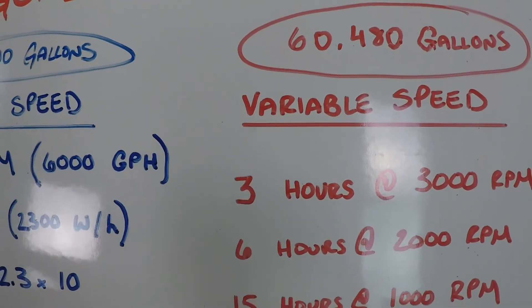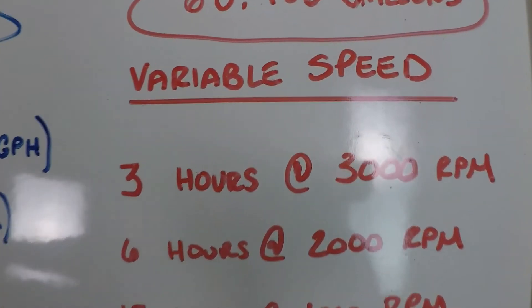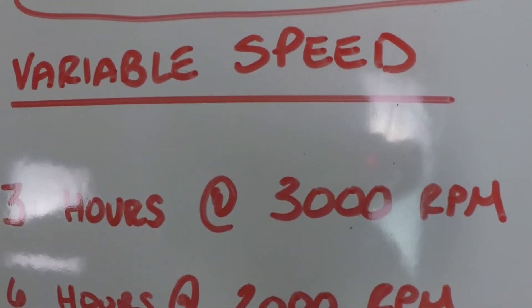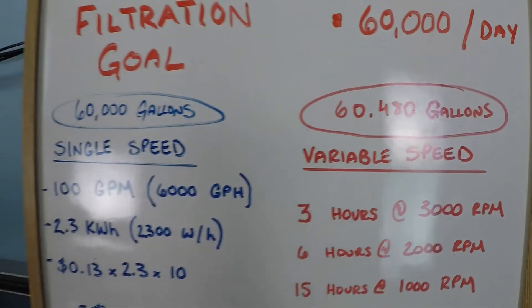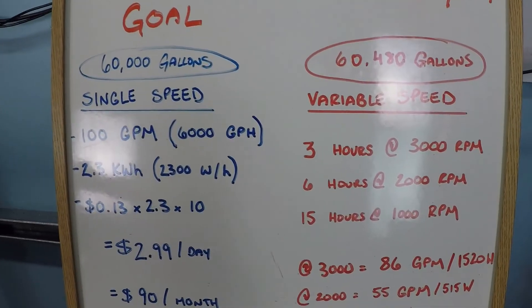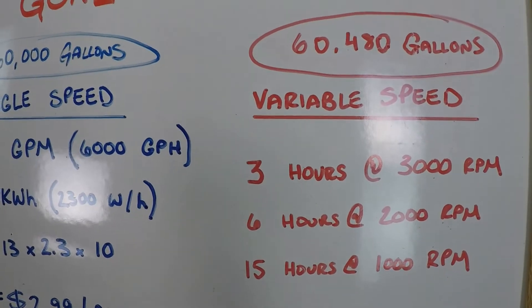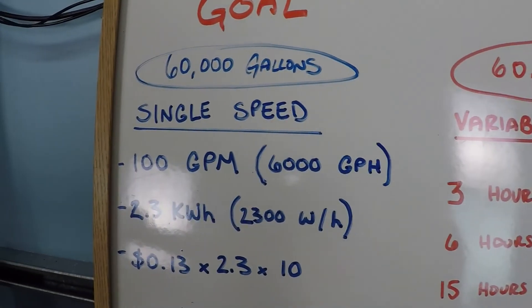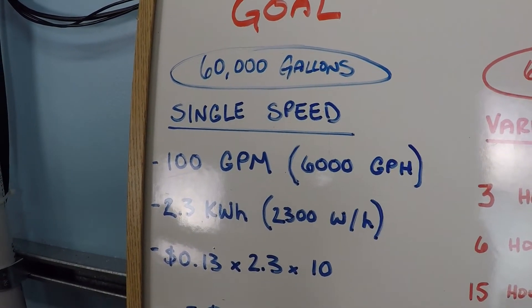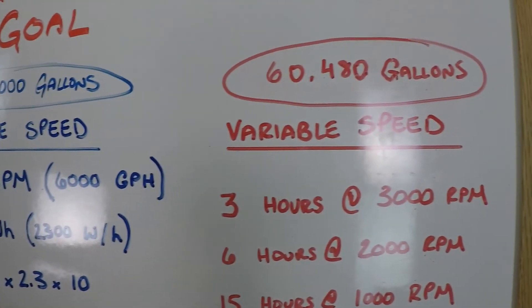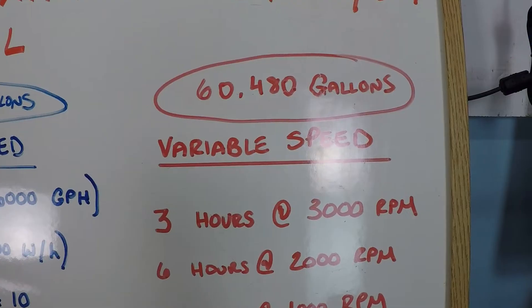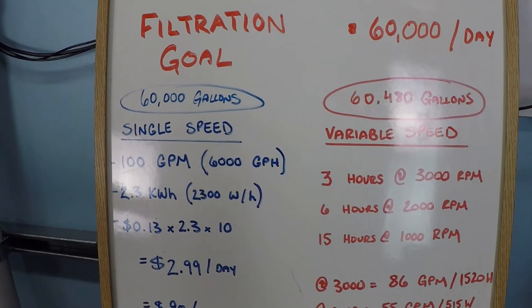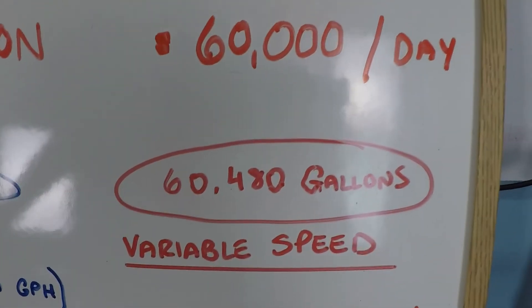Every hour that your variable speed pump is off is another missed opportunity for you to save a lot of money. And I'm going to show you how here. So with this schedule, the first thing you'll notice is that our top speed isn't 3,450 RPM. It's 3,000. Why would that be? Well, the reason is you can get a lot of flow at 3,000 RPM, almost as much flow as you do at 3,450. But even a small reduction in speed results in a huge drop in power consumption. Let's take a look.